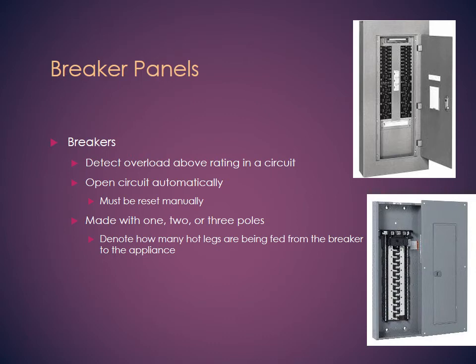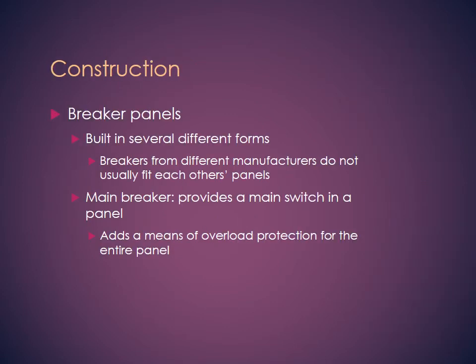Breaker panels, again, if you look here, this is where you clip your circuit breaker, and you see this is the hot line, and this is our neutral. If you have a double breaker, it clips onto two hot lines, and they call those lugs because they can clip to them. Breakers detect overload based on the rating. If it's 15 amp and we draw 17 amps or 16 amps, it will trip, so you can go and reset it manually. They can be 1 or 3 poles depending on the setup and how many legs there are. One pole could be for 110, 2 poles for 220, and 3 poles could be for more than 220, or could be 3 phase. They are constructed in different ways.